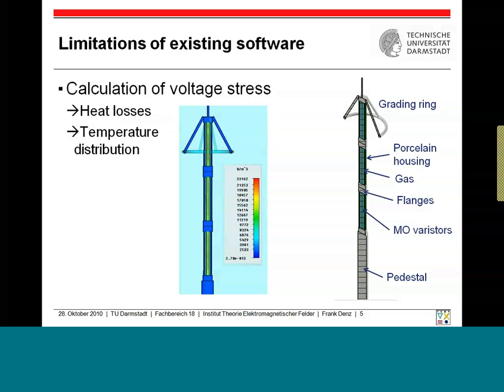For this purpose, here in this case, I assume a certain value of electrical conductivity and of permittivity. As you can see in the picture, the heat losses are almost the same inside the surge arrester stacks.